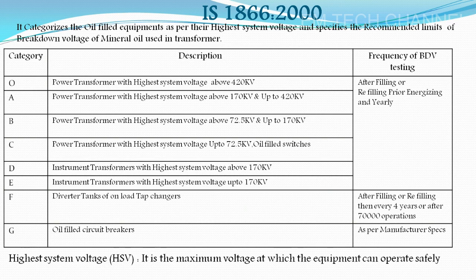It is the maximum voltage at which the equipment can operate safely. Normally, we call voltage levels 400 kV, 33 kV, 110 kV like that. Even though it is a system voltage, the manufacturer gives an additional loading factor so that even if the voltage is slightly increased, the equipment will not get damaged, and hence it is called the highest system voltage. So this standard is purely based upon the highest system voltage, and it categorizes the equipment based only upon the highest system voltage and not upon the normal system voltage.